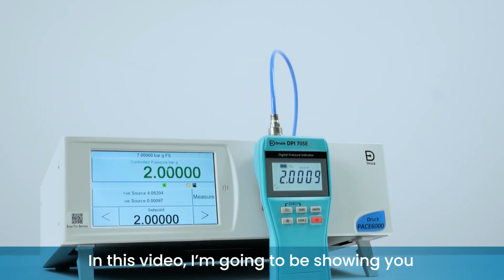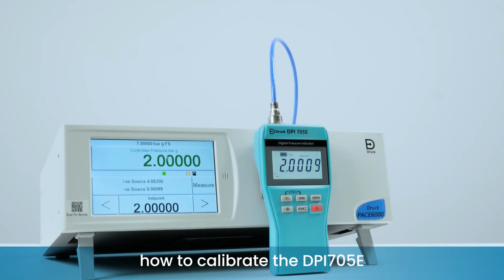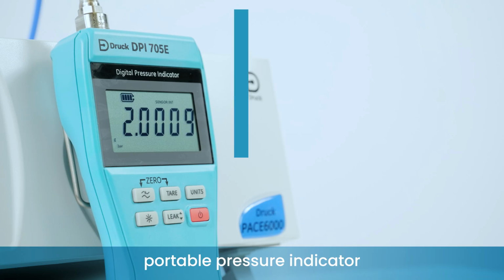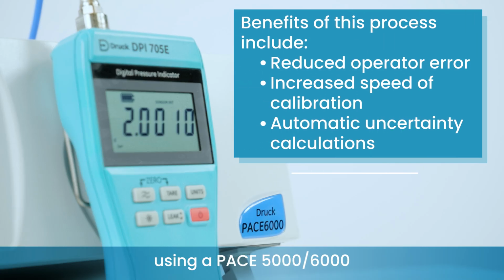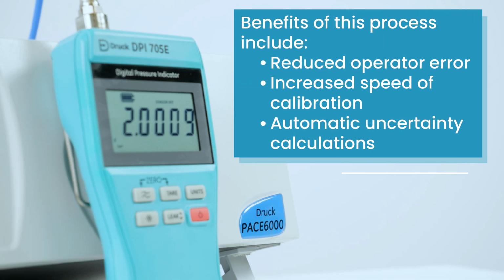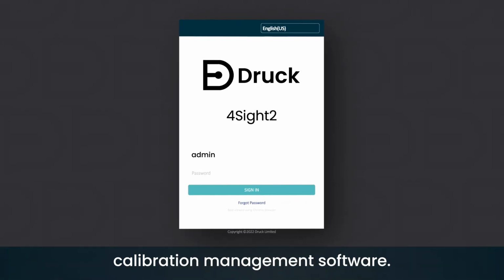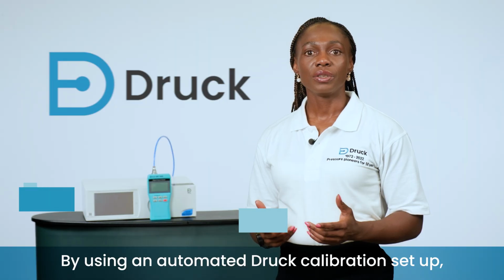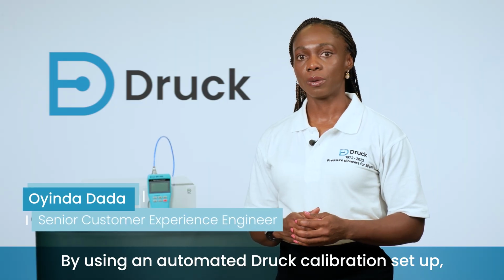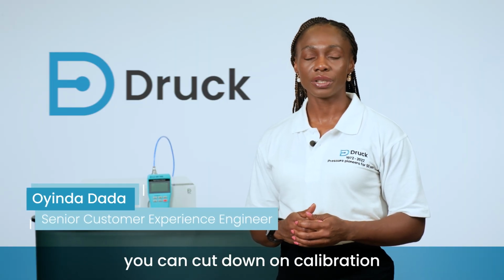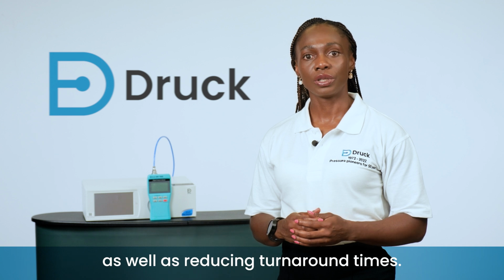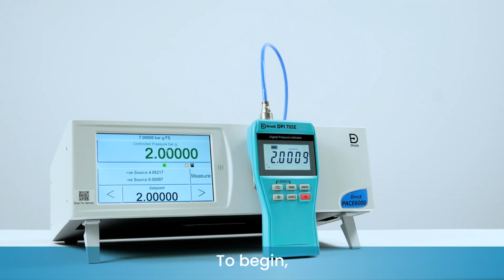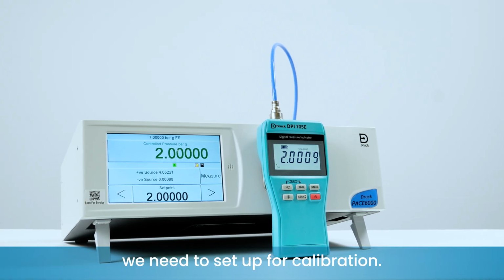In this video, I'm going to be showing you how to calibrate the DPI705E portable pressure indicator using a PACE 5000-6000 pressure controller and Foresight 2 calibration management software. By using an automated calibration setup, you can cut down on calibration and shipping costs, as well as reducing turnaround times. To begin, we need to set up for calibration.